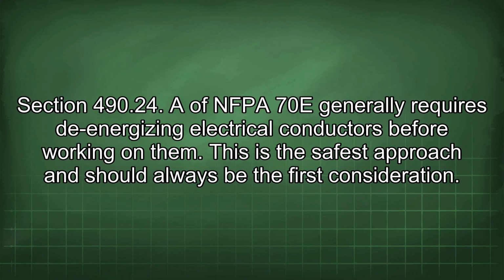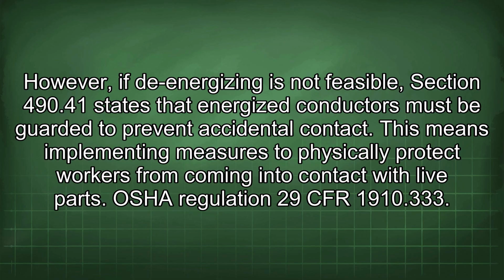Section 490.24 of NFPA 70E generally requires de-energizing electrical conductors before working on them. This is the safest approach and should always be the first consideration. However, if de-energizing is not feasible, Section 490.41 states that energized conductors must be guarded to prevent accidental contact. This means implementing measures to physically protect workers from coming into contact with live parts.